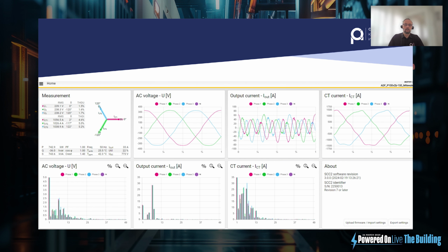And here you can see the results of the harmonic mitigation. So on the left-hand side, in the bottom corner, we've got 1,000 amps of load, and we were keeping the THDI under 5% and resulted in the voltage distortion being under 2%, which is everything's happy.